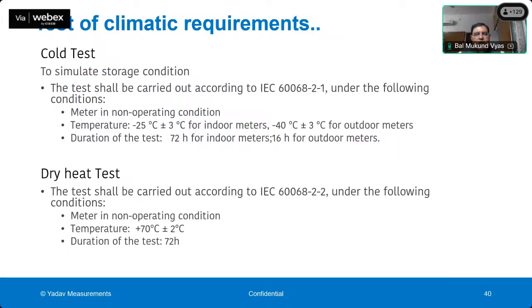If it is an indoor meter, then the meter is kept at -25 degrees centigrade for 72 hours. And if it is an outdoor meter, then it is kept at -40 degrees centigrade for 72 hours. After 72 hours, the meter is again tested for its accuracy and functionalities. Similarly, for high temperature, it is subjected to 70 degrees centigrade for 72 hours. So these two tests actually simulate the storage of the meter. During storage, the meter's accuracy and its functionality should not be affected.